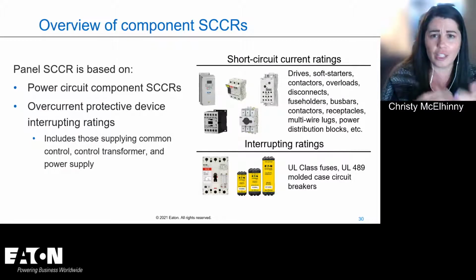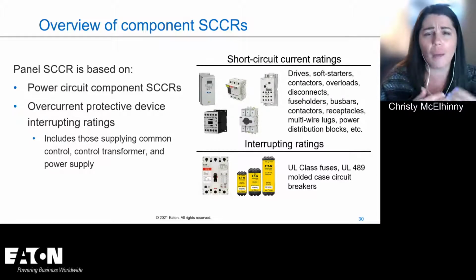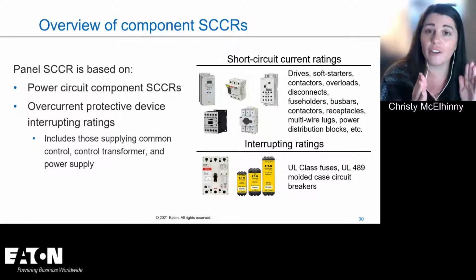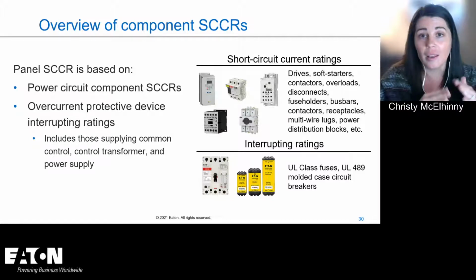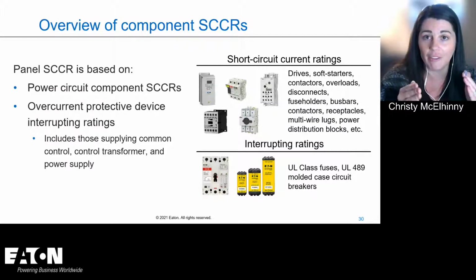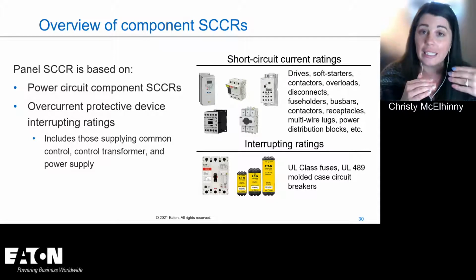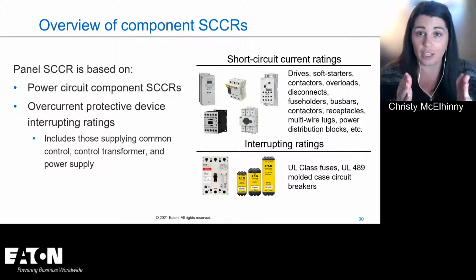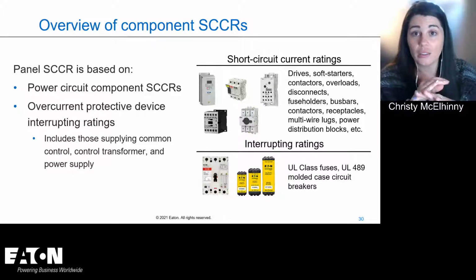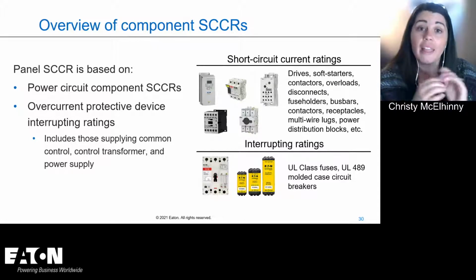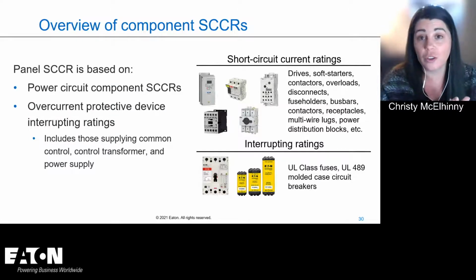So that's never going to change depending on what's upstream from it, right? If I am a breaker and I can safely interrupt 10,000 amps, you could put 14 fuses in front of me, but I can still only ever safely interrupt 10,000 amps. The amount of current that I see doesn't matter. It's just defined as how much I can interrupt. So interrupting ratings can't change, right? That's different than short circuit current ratings, right?